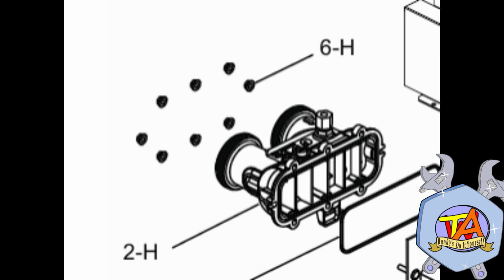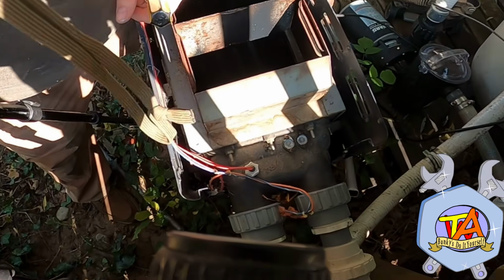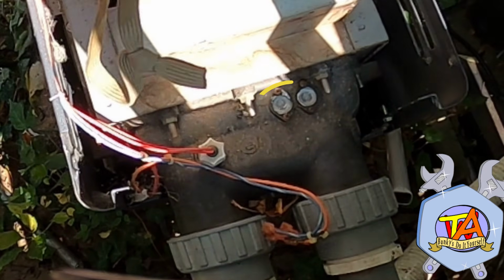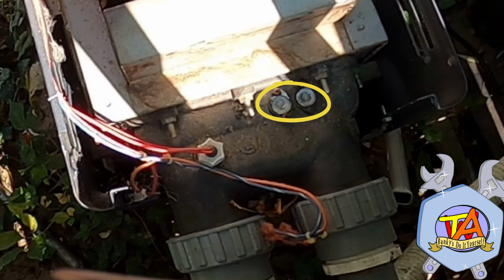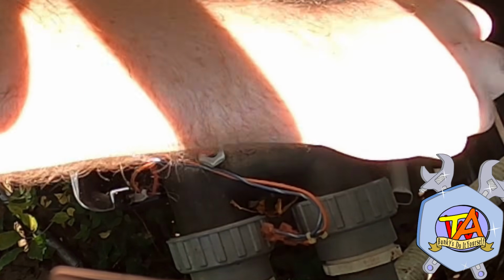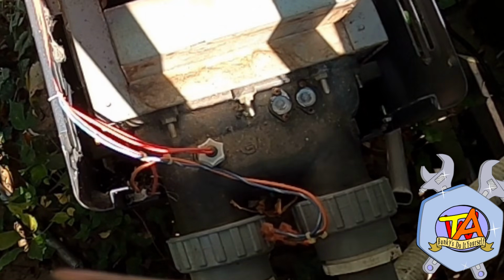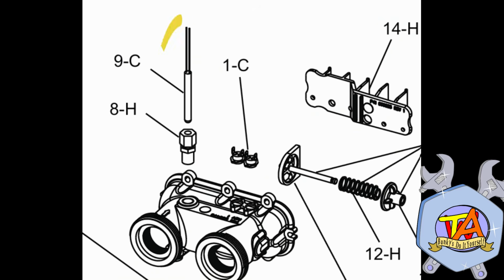As stated earlier, they're on the inlet and outlet of the unit, and here I am installing them. You need to add a thermal compound between it and the unit for better heat transfer. That's that silver stuff in the hole. In the same area, we have an analog temperature system and a flow sensor.